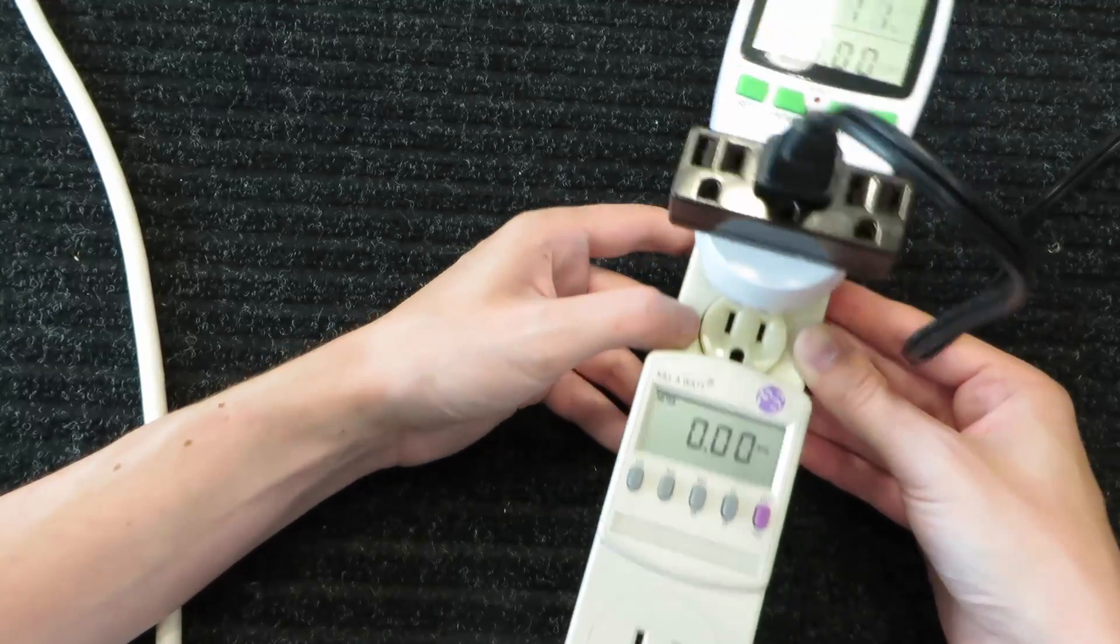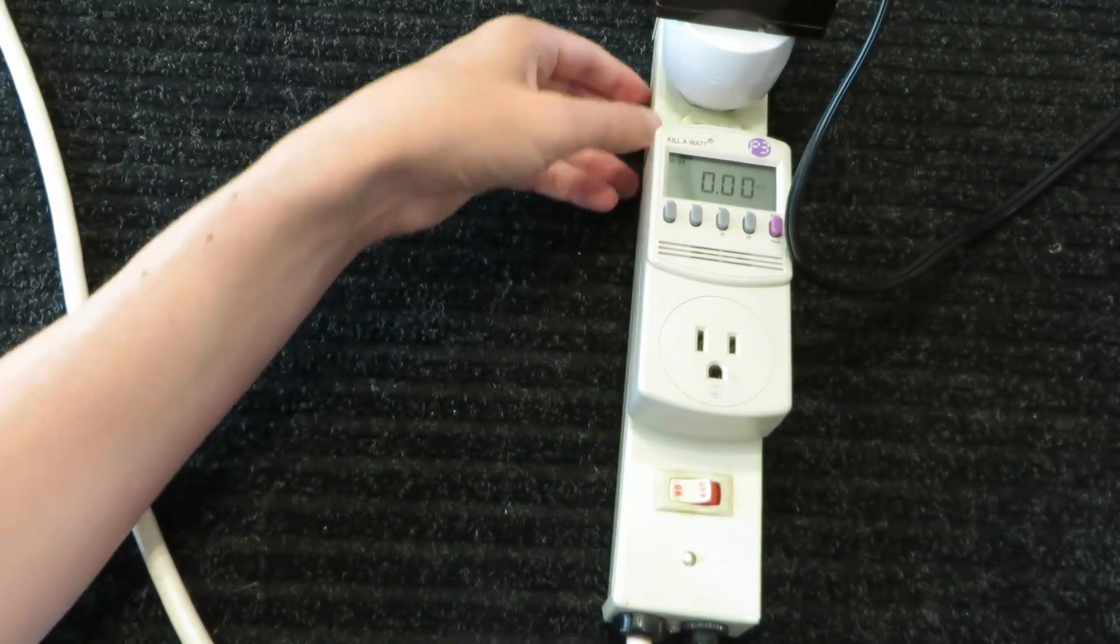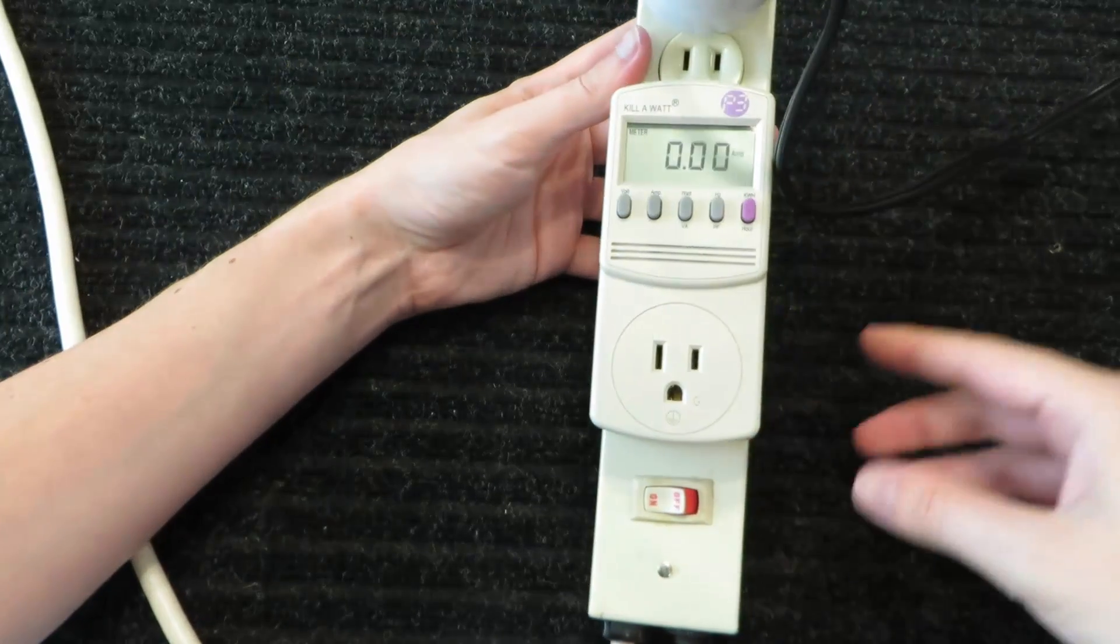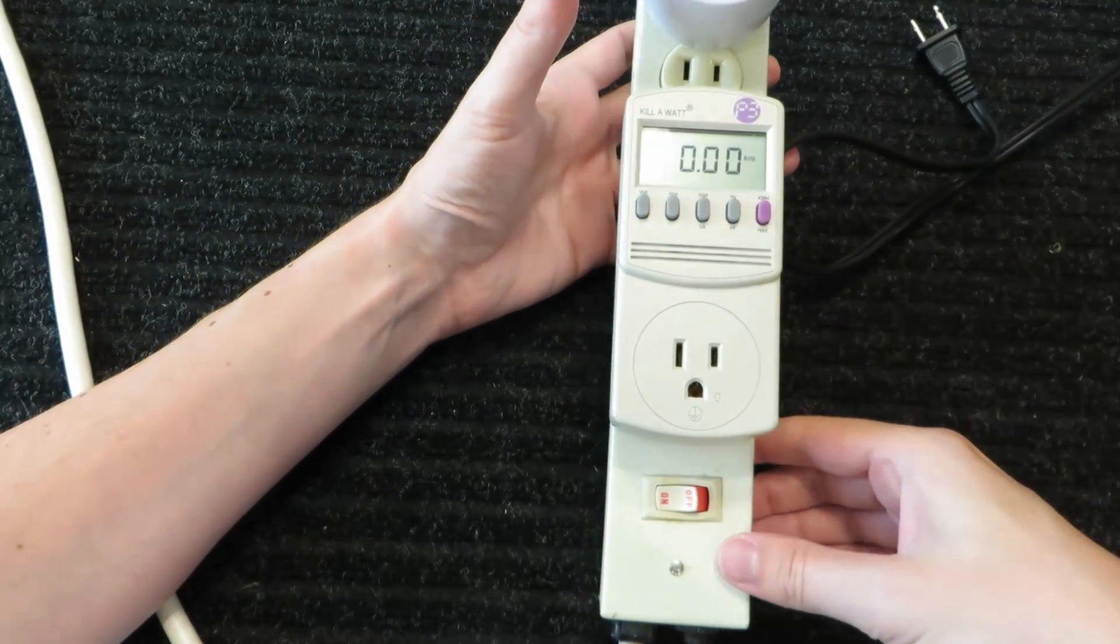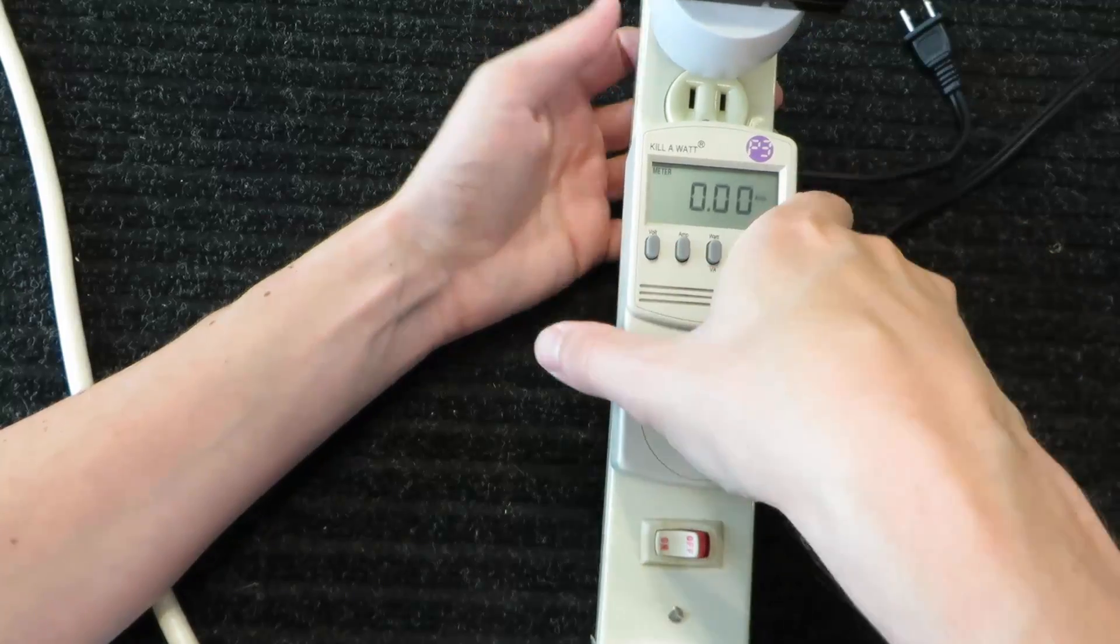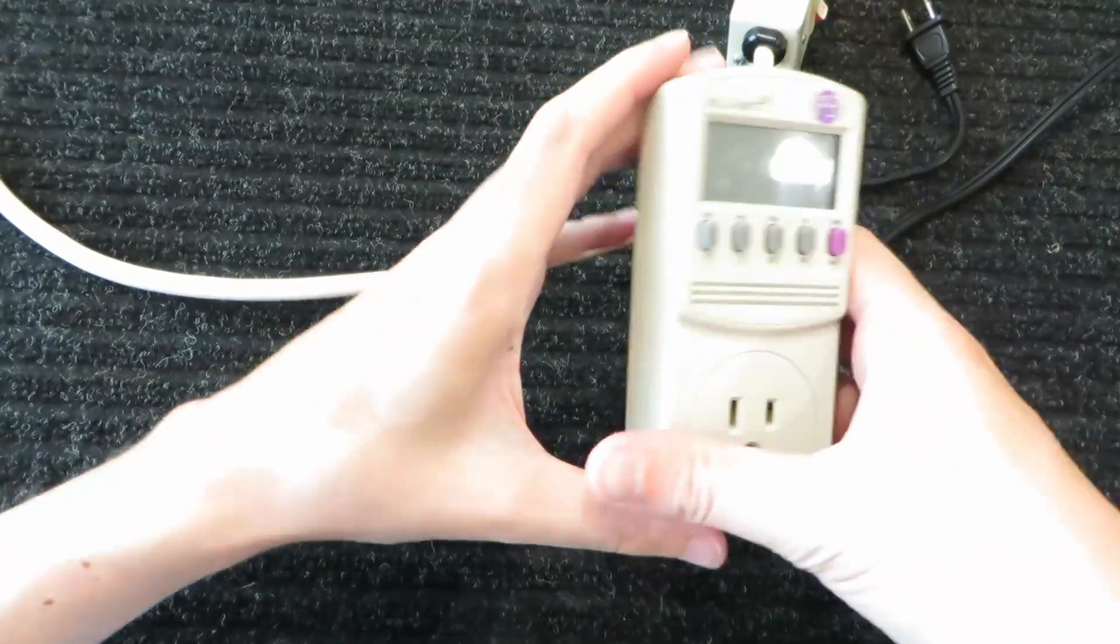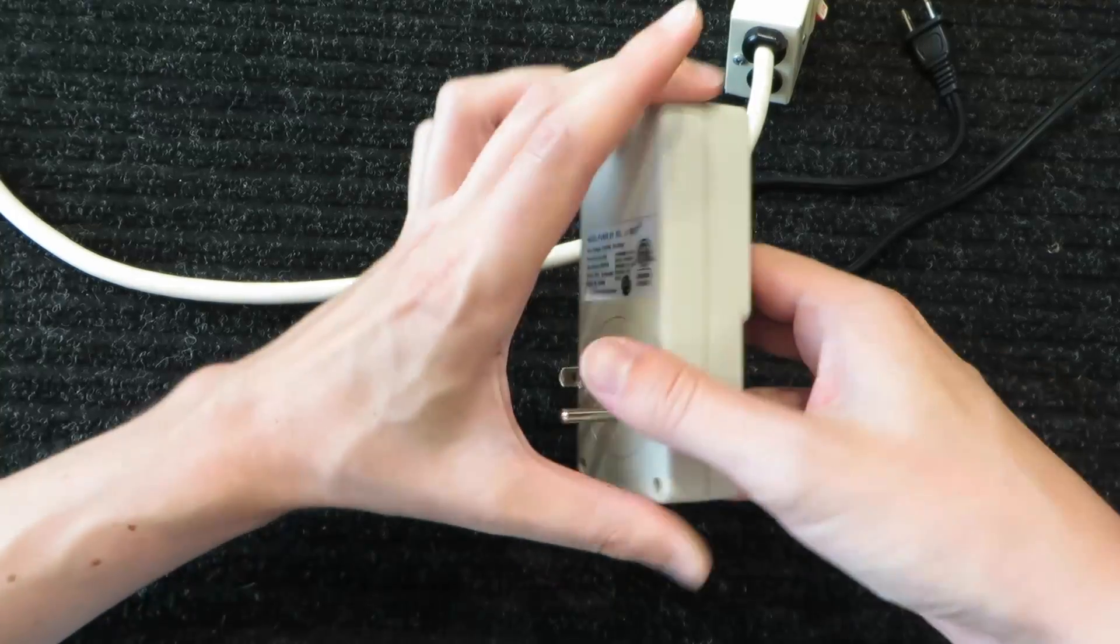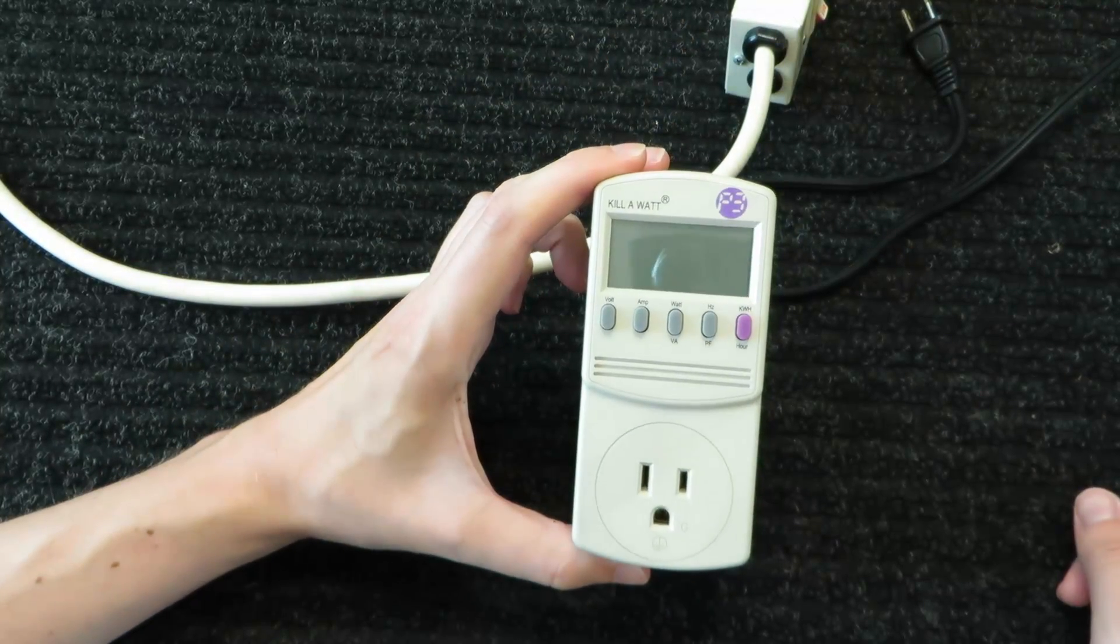Very close. So this meter is repaired. Nothing I did inside should change its accuracy whatsoever or its ability to monitor power factor or anything like that. My favorite little meter here is now repaired in good working order.